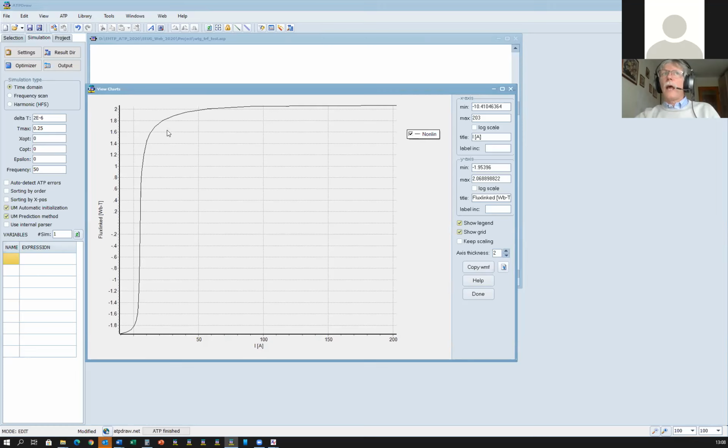If the voltage is higher, you can simply multiply with the new voltage level. If the power is higher, you can simply multiply on this curve on the current scale. Even if the frequency changes from 50 to 60, you can adjust this curve.